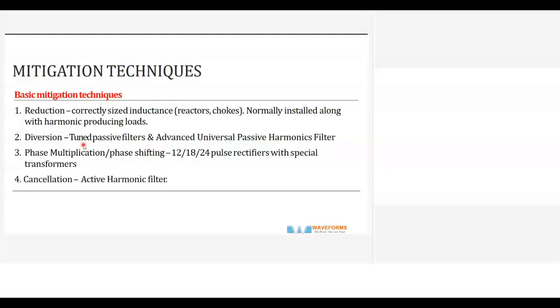In the universal passive harmonic filter, besides diversion, we use other techniques also, like mutual inductance and phase shifting. That's why it is a much more effective filter than the tuned passive filter. Tuned passive filters have other issues. When there are other harmonics, it can interact. When the source impedance and the load impedance change, the tuning can change again. When capacitor efficiency comes down, the tune doesn't work properly. So there are a lot of issues with tuned passive filters. They are really, I would say, outdated now.